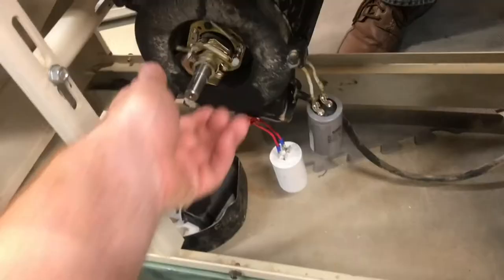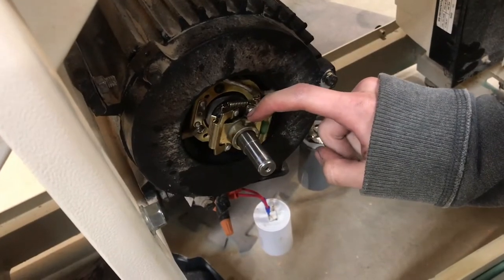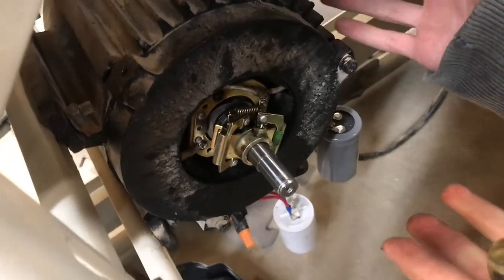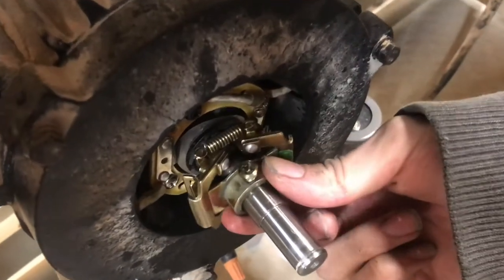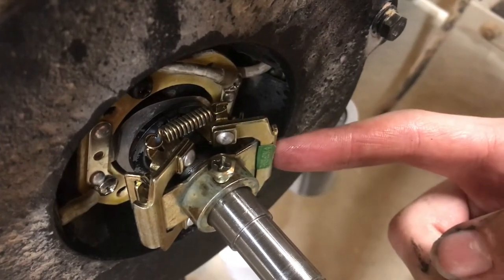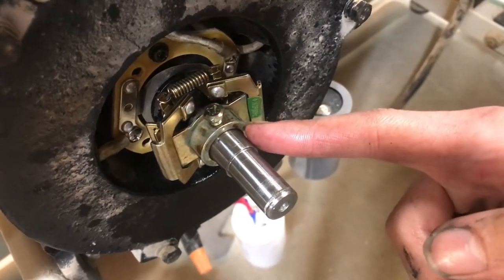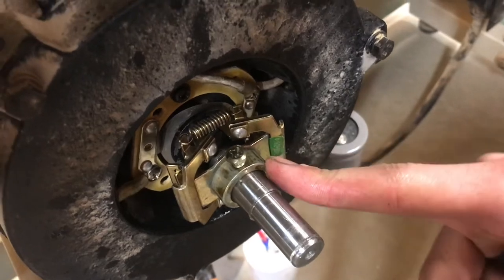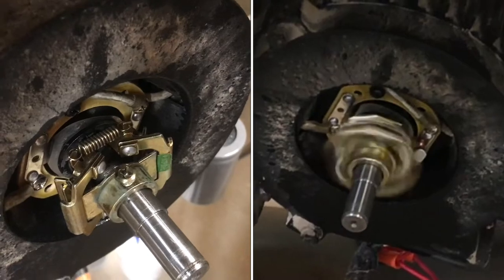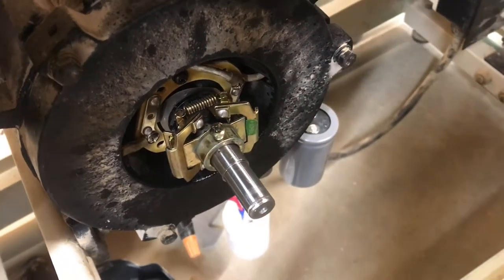This motor was not starting, and we determined that the starter windings were not engaging or maybe they were broken. What was actually happening was the centrifugal switch had slipped on the shaft, so that when the motor was off, the start windings were not even engaged. By pushing the centrifugal switch in farther, that caused it to actually engage the starter windings, and that simple fix makes the motor work.